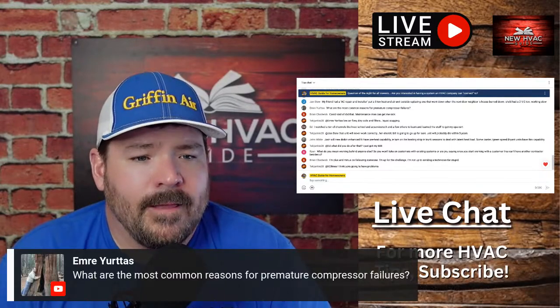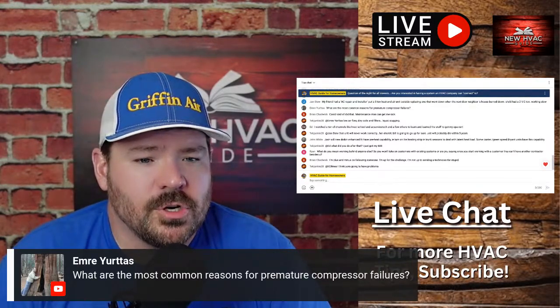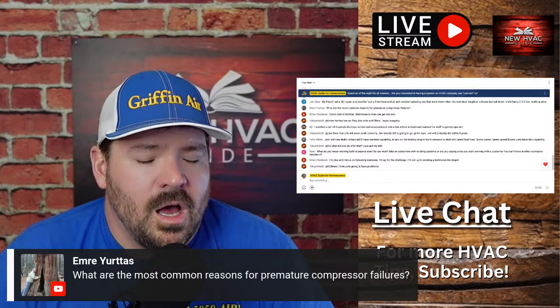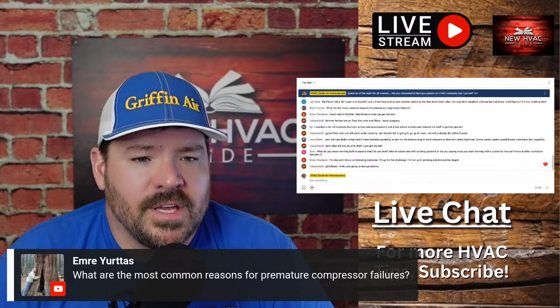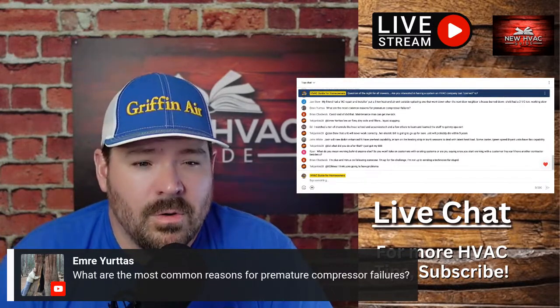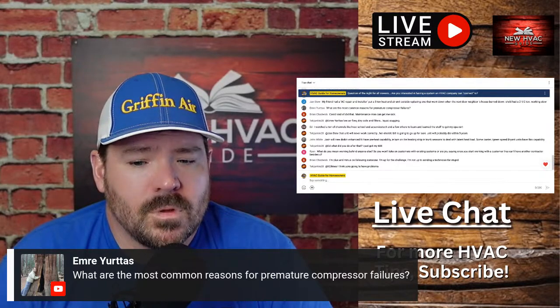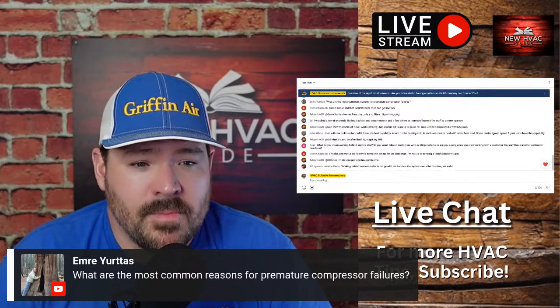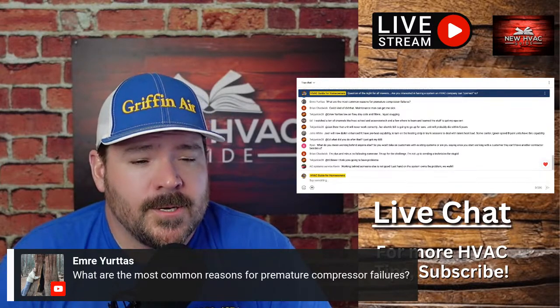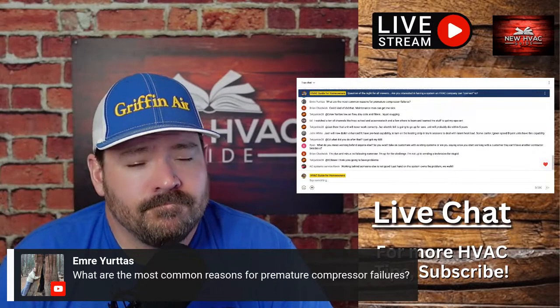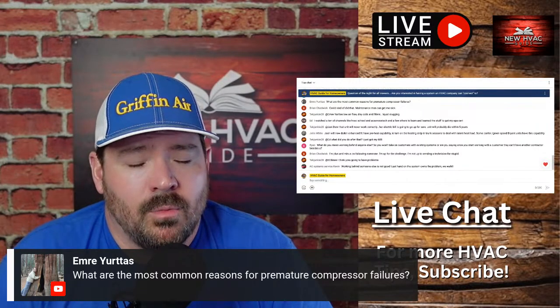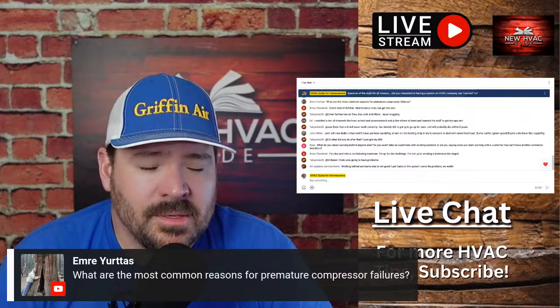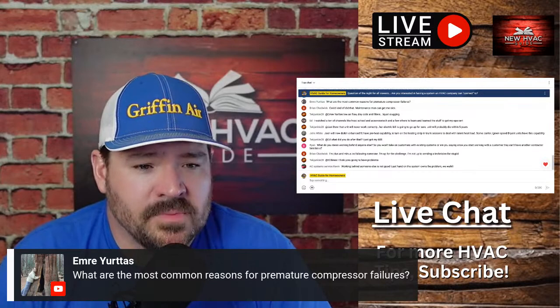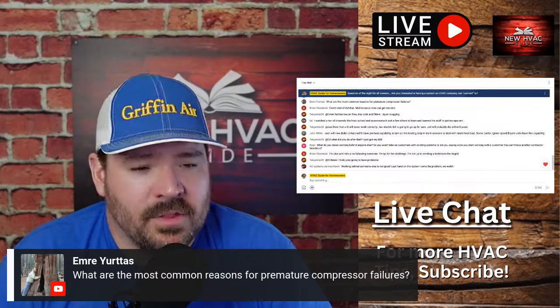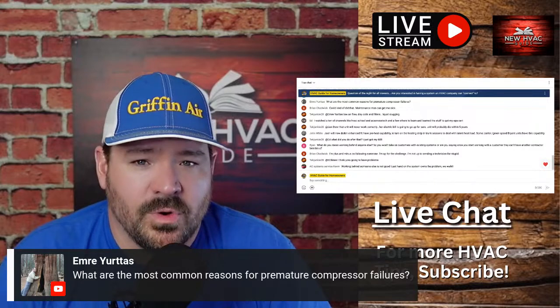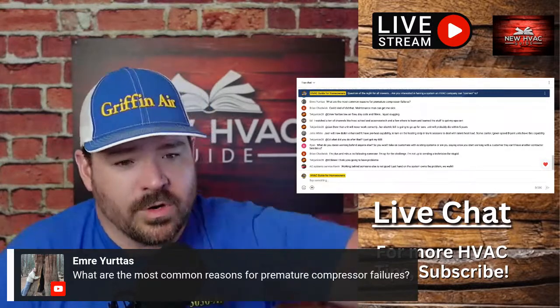Emery says, what are the most common reasons for premature compressor failures? Poor maintenance, poor installation of the heating and air system, poor airflow would be one, and dirty power might be another, like brownouts and surges. Refrigerant not being charged correctly, possibly. You guys might think I'm nuts on that, but I was just talking to somebody the other day who didn't know what subcool was, and they'd been doing that work for a competing company. I was just floored.